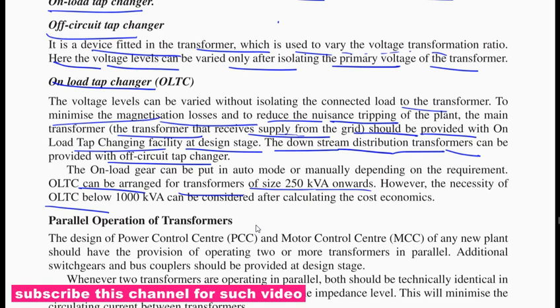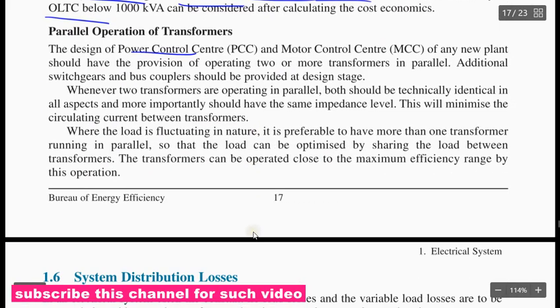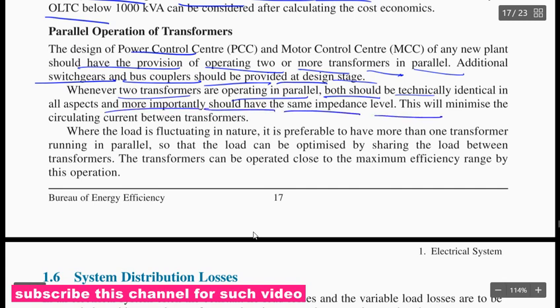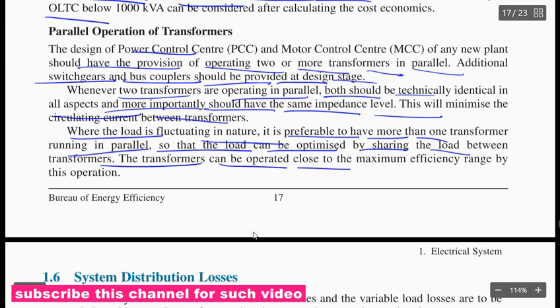Parallel operation of transformers. The design of the power control center and motor control center of any new plant should make provision for operation of two or more transformers. The additional switchgear and bus couplers should be provided at the design stage. Whenever two transformers are operated in parallel, both should be technically identical in all aspects. More importantly, they should have the same impedance level. This will minimize the circulating current between the transformers. When the load is fluctuating in nature, it is preferable to have more than one transformer running in parallel so that the load can be optimized by sharing it between the transformers, and the transformers can be operated close to maximum efficiency range.